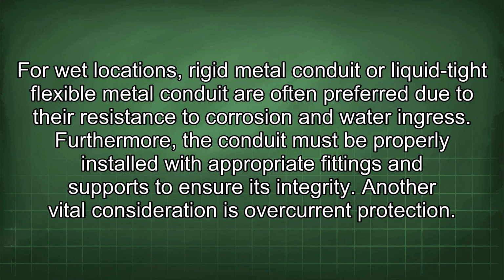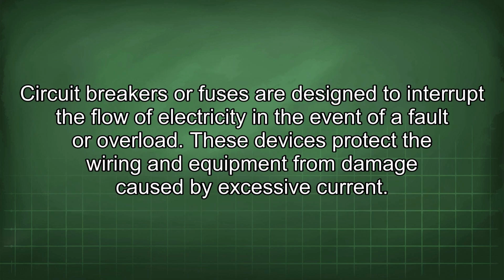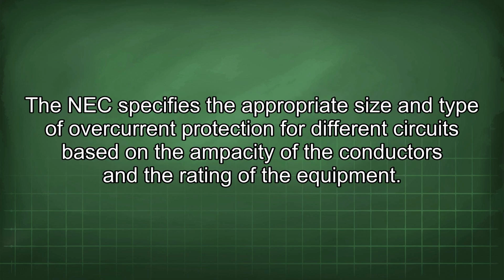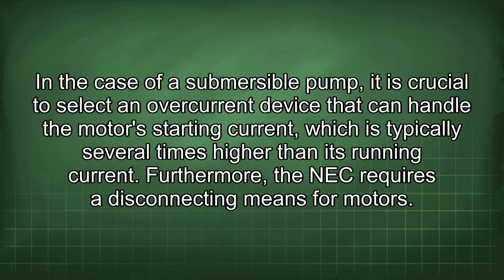Another vital consideration is overcurrent protection. Circuit breakers or fuses are designed to interrupt the flow of electricity in the event of a fault or overload. These devices protect the wiring and equipment from damage caused by excessive current. The NEC specifies the appropriate size and type of overcurrent protection for different circuits based on the ampacity of the conductors and the rating of the equipment. In the case of a submersible pump, it is crucial to select an overcurrent device that can handle the motor's starting current, which is typically several times higher than its running current.